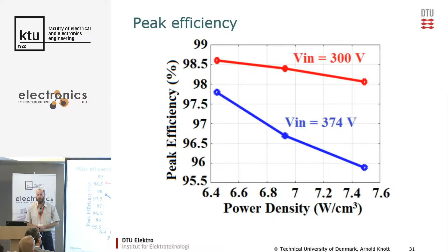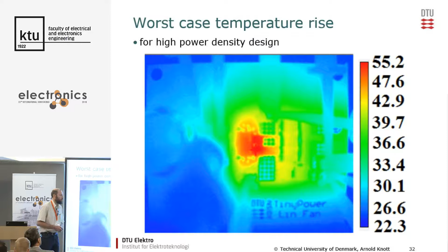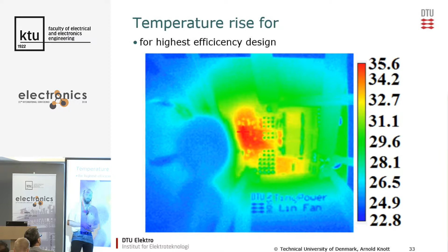A good way of verifying the design is also keeping an eye on the temperature. We usually always have a thermal camera mounted on top of our designs. For the high power density design, we were allowing a rather high temperature rise, 33 degrees Celsius above the ambient temperature of 22 degrees Celsius. And for the highest efficiency design, we were going rather low on that one. We were at only 13 degrees above the ambient temperature, which was also about 23 degrees.